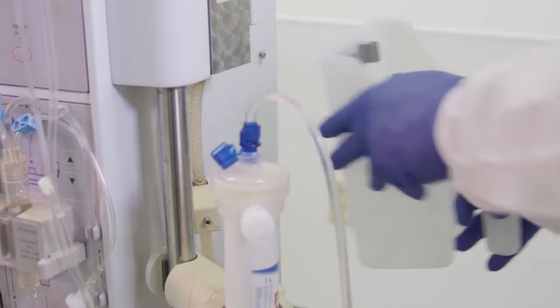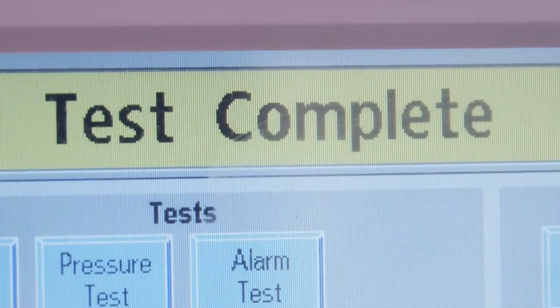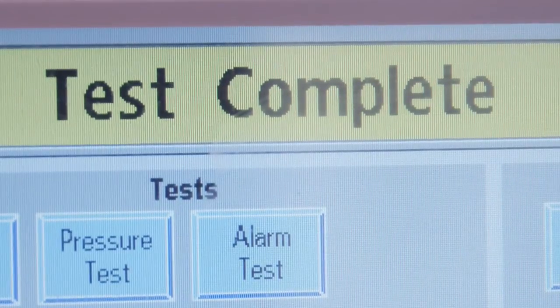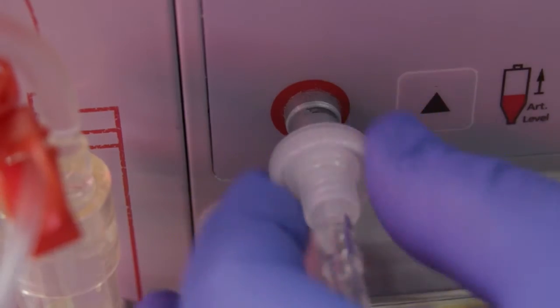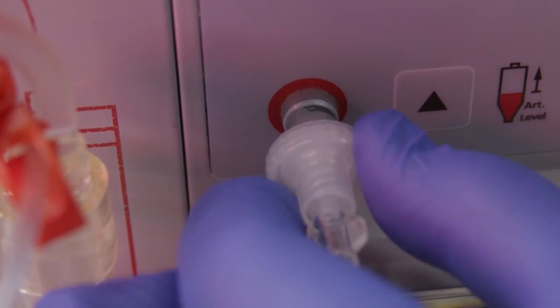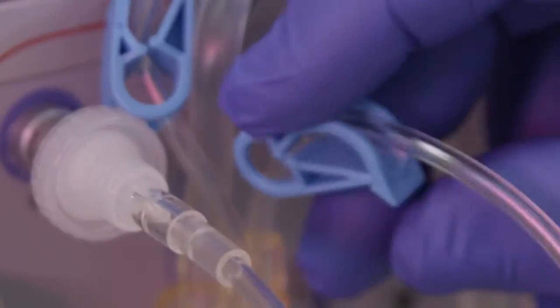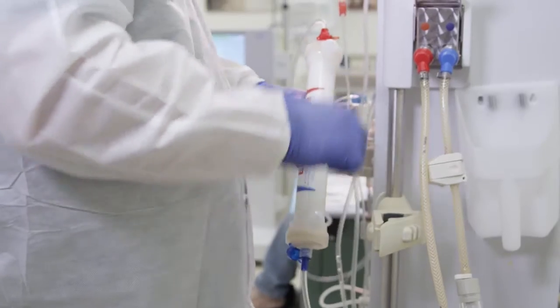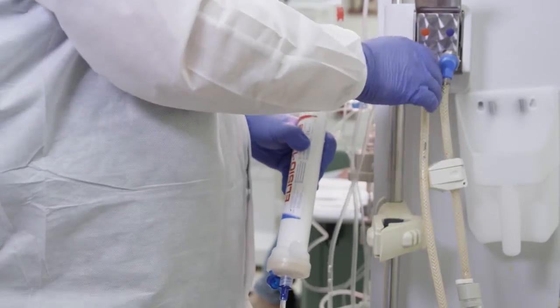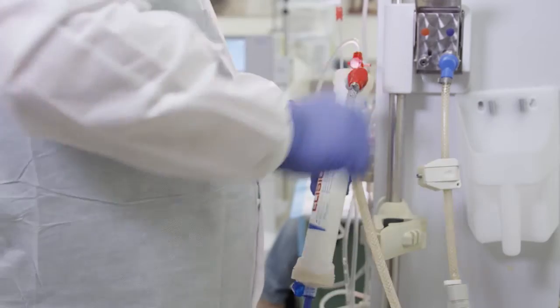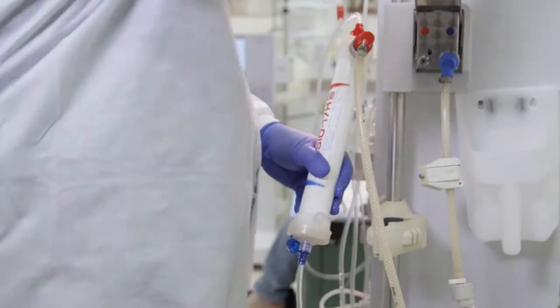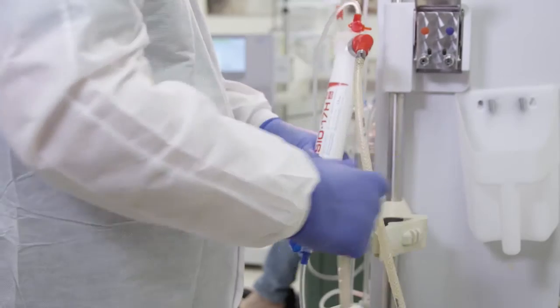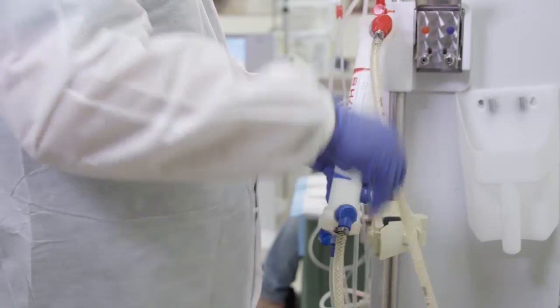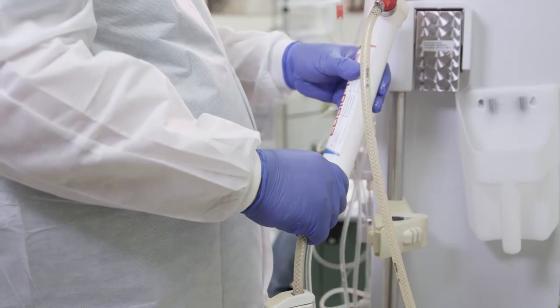Empty and rinse the priming container. Verify all safety tests on machine are completed successfully. Press the reset button. Verify the transducers are tightly fastened to the lines, and then attach the arterial and venous pressure transducer protectors to the machine. Open the small clamps. Open the shunt door. Connect the dialysate lines to the dialyzer and then close the shunt door. Remove the dialyzer from the holder and rotate until the dialysate compartment is completely filled with dialysate. Place the dialyzer back in the holder with venous end up.